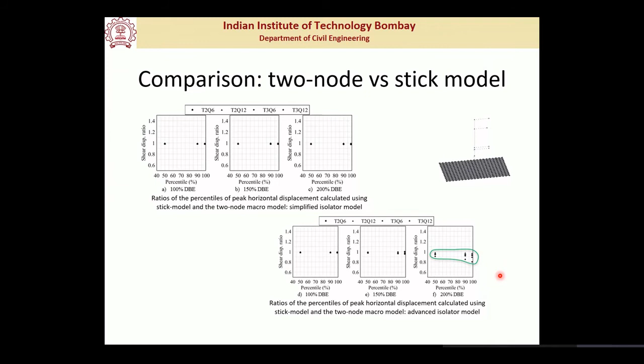So finally, with respect to each of these properties that you see here, we are suggesting which individual characteristics need to be considered in the response, and at what kind of intensities. Heating need not be considered at the design basis earthquake, but buckling may need to be considered at the design basis earthquake. Cavitation need not be considered. Axial stiffness dependence need not be considered. Same for the shear stiffness. So at DBE, you may only need to consider the variable buckling load.